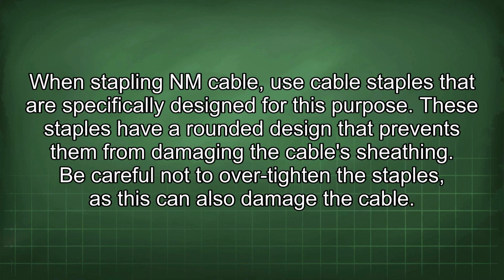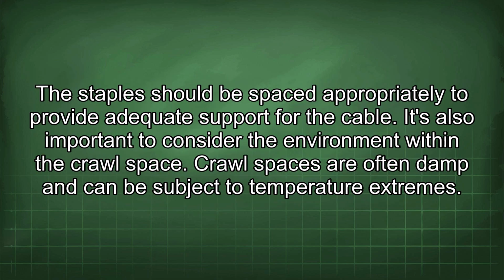When stapling an NM cable, use cable staples that are specifically designed for this purpose. These staples have a rounded design that prevents them from damaging the cable sheathing. Be careful not to over-tighten the staples, as this can also damage the cable. The staples should be spaced appropriately to provide adequate support for the cable.